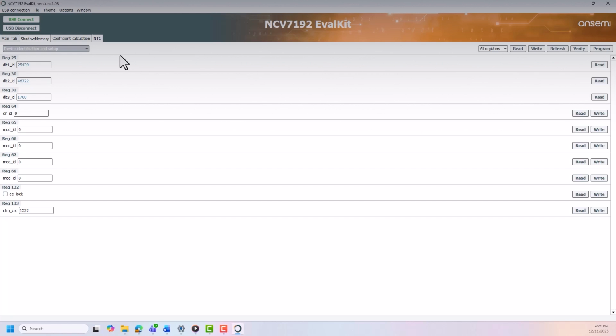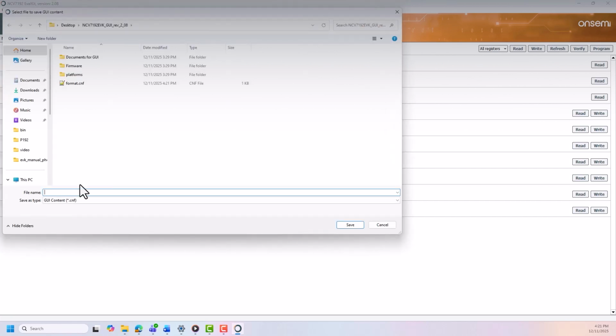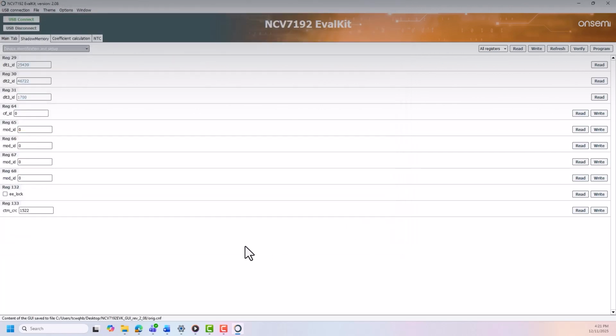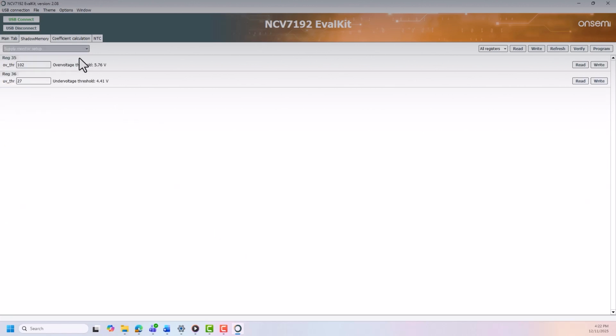After entering calibration mode, I strongly recommend saving original device content by clicking on File, and then on Save Content to File button. Let's enter a file name. I recommend saving original device content because on certain memory locations there are stored some temporary trim coefficients from production testing. Those coefficients will be important for accurate calibration and will be later rewritten by final calibration coefficients or by our experiments. On the left upper side, you can select certain register group. On the right side next to each register, you can read or write specific register, or in the upper right corner, you can read or write all device registers at once. Those read and write operations have impact only on shadow memory content.